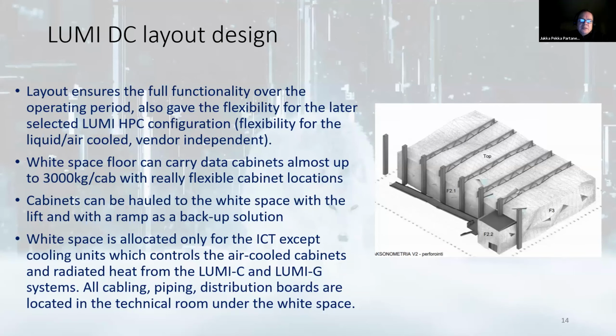And the white space floor can carry, of course, we knew that those are heavy cabinets, almost 3,000 kilos per cabinet that we can load onto the white space. And there's a lift, so we can lift those cabinets directly to the level of the white space. And as a backup, we also have a ramp, which we can use if the lift is not working.